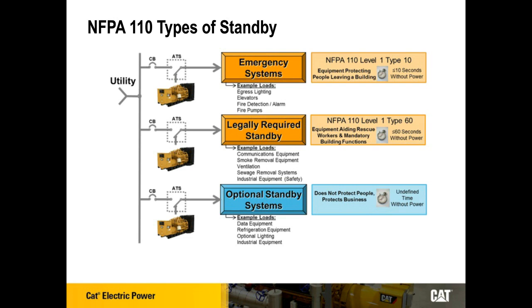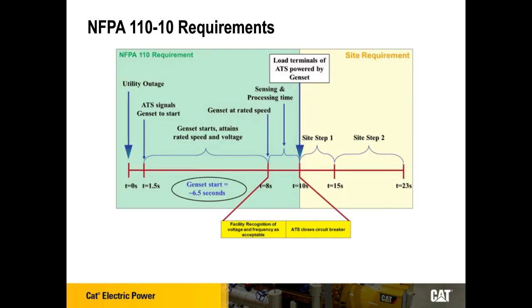So, like we talked about, NFPA 110 Type 10 is probably the most commonly specified NFPA emergency system requirement. It's often referred to as 10-second start, but that can be a little bit of a misnomer. So to clarify that, we'll walk through the timeline of what happens in an emergency standby power system when the utility power goes away.